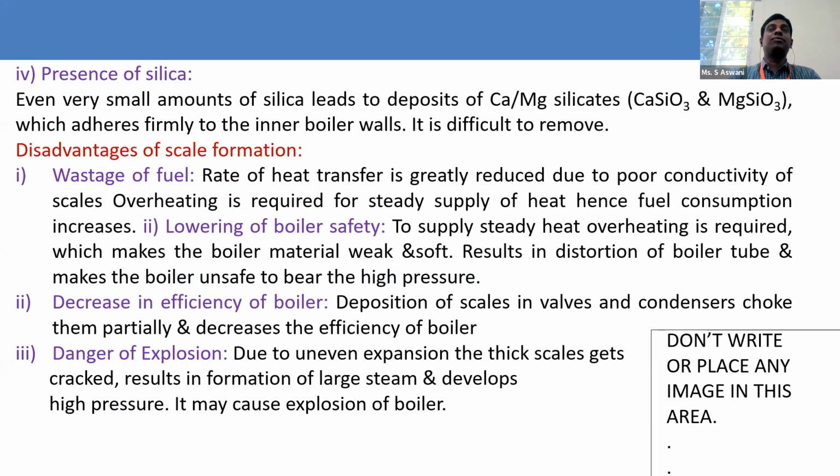And the presence of silica is another cause. If the water has any silica particles, very fine silica particles, even a small amount of silica, it also leads to deposits of calcium and magnesium silicates. The silica particles are converted to calcium silicate and magnesium silicate, which adhere firmly to the inner wall of the boiler. So it is very difficult to remove this type of silica deposit.